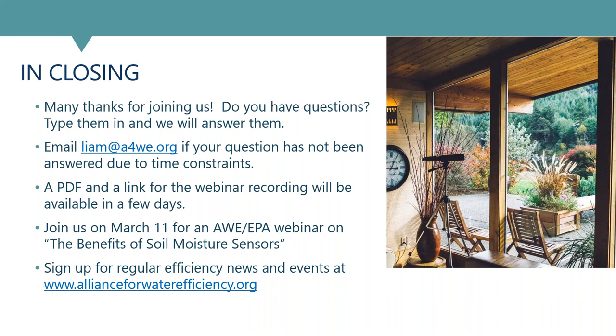This is Anaki. I'll just add that if you can't get into a CII facility, a lot of times people don't understand when a leak is actually a leak. If there's constant flow from a complex piece of equipment, it's complex enough to where it gets ignored. I've seen cooling towers that have run for literally years because when somebody started, the machine was already running nonstop, so they assumed it was supposed to do that. These things can go on and on without people realizing it's a leak because it's going into a drain. The goal is to empower CII facilities to be aware of those vulnerability points themselves. An audit finds things at one point in time, but if staff are walking by every single day, they have an opportunity every single day to identify a problem.